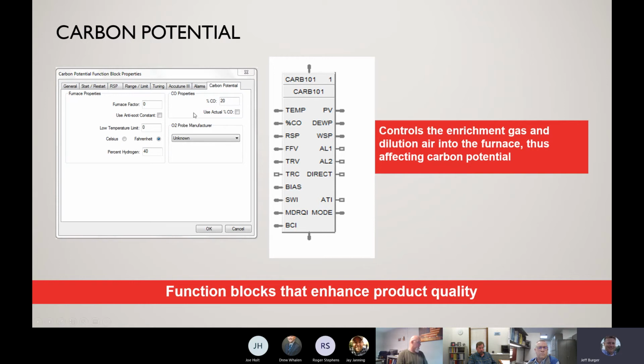So for carbon potential applications, if you click on this function block, it goes into a configuration worksheet. On the left-hand side it gives you a lot of the standard tabs to configure different ranges and different inputs into that function block to accomplish that control. You also see down here it has O2 probe manufacturer. If you click on that, it will give you all the O2 probe manufacturers, like Super Systems and others, that you can pick from, and the carbon control loop will then understand the input coming from that probe and be able to use it in that control algorithm.